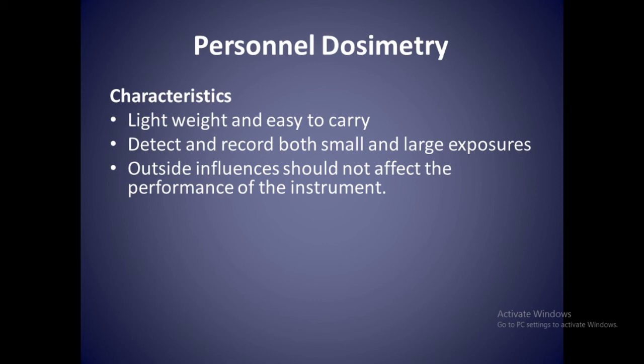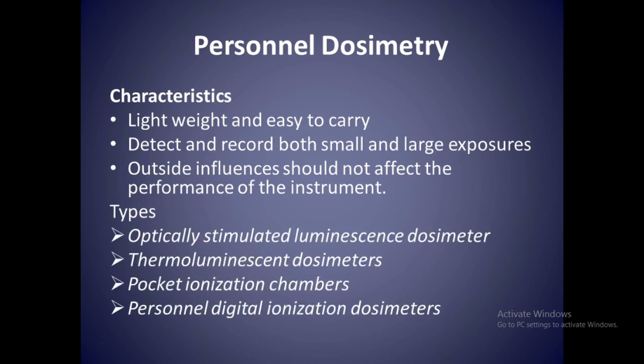As many employees in a healthcare facility may be assigned to wear radiation monitors, the monitors are required to be reasonably inexpensive to purchase and maintain. This permits healthcare facilities to use a large number of monitors in a cost-effective manner. Four types of personal dosimeters are currently widely used: optically stimulated luminescent dosimeters, thermoluminescent dosimeters, pocket ionization chambers, and personal digital ionization dosimeters.